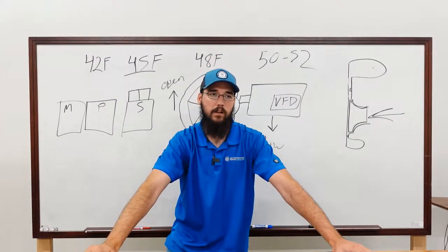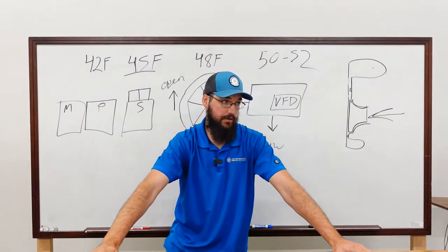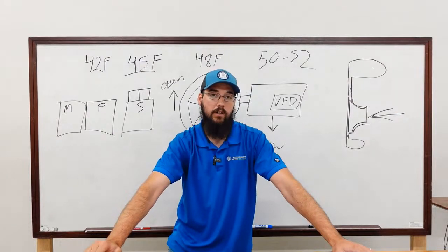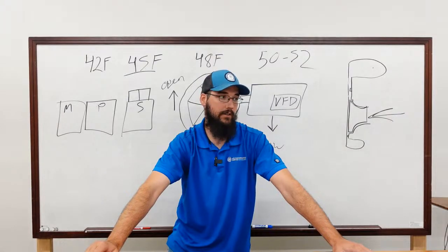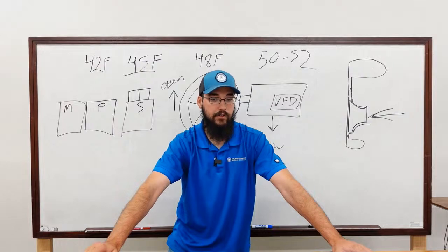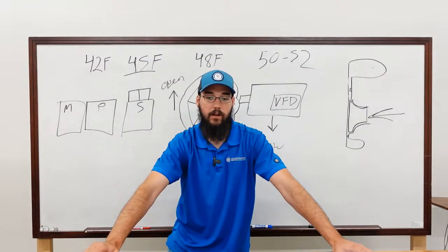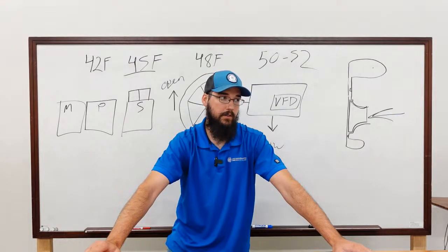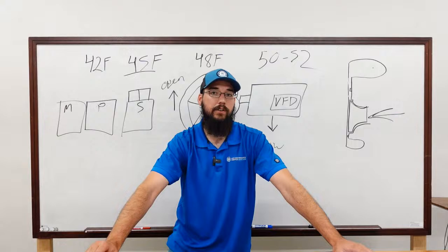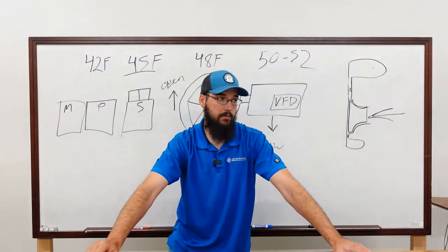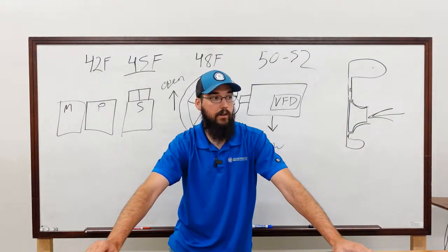But a lot of the time, especially in a low load condition, as that machine begins to unload, you'll hear the compressor begin to kind of growl, and it's got a grumble to it. And it genuinely begins to sound unbalanced. Because that's basically what's happening.